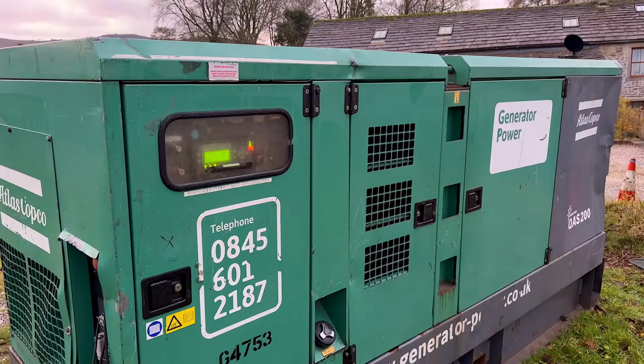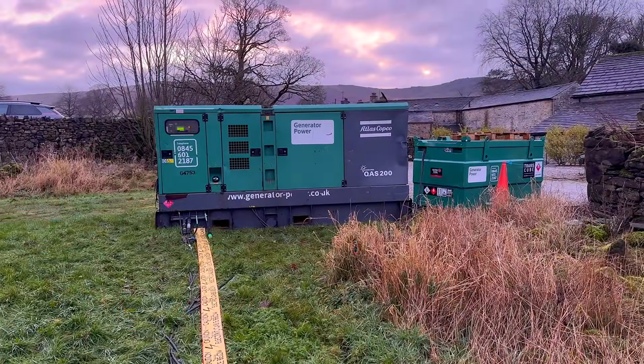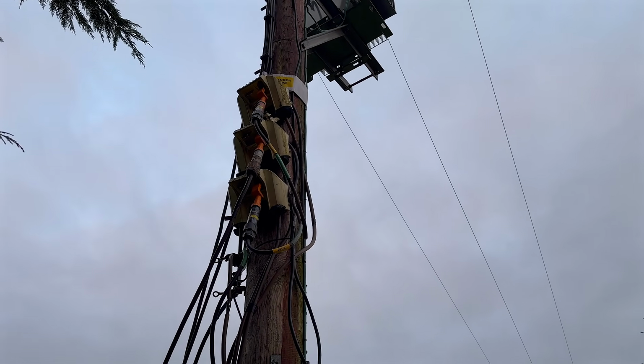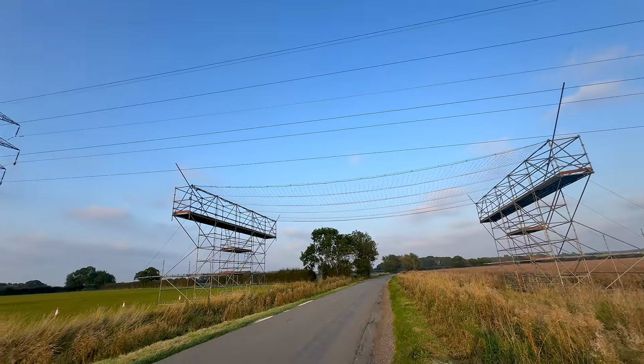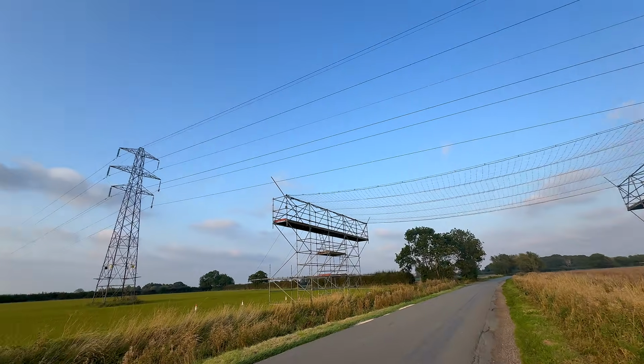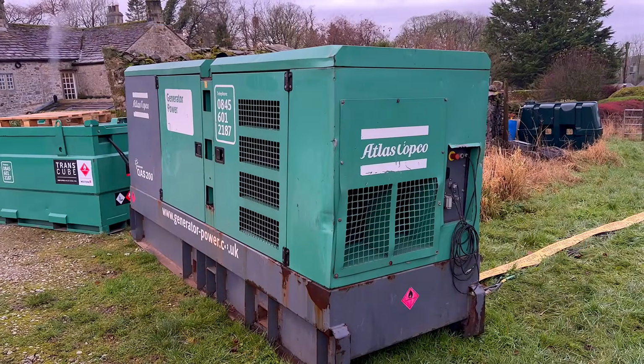Generators are another good example. If a generator is installed for standby purposes and the main supply is lost, the generator starts and takes over. At that point, the distributor may be working on the supply system, so the generator must have its own independent earth. Again, this is achieved by using an earth electrode.